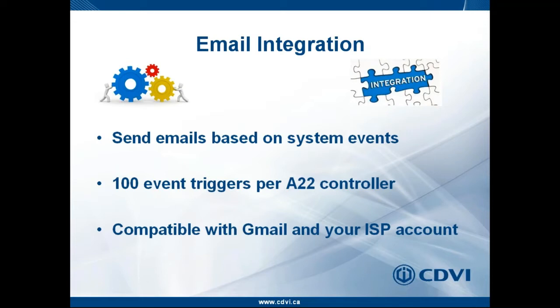Email integration: any event that the system can generate can be used as a trigger to send an email. Very often we will use alarm situations — door forced open, door left open, card access events, access denied events — and we will be able to send an email to three individual email addresses. The Atrium controller will be able to fire off an email on these types of events.